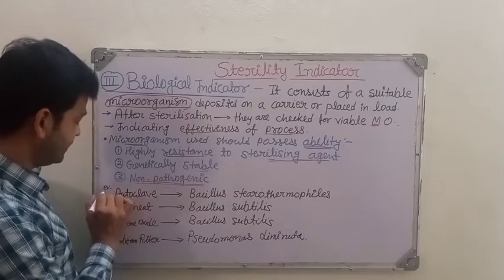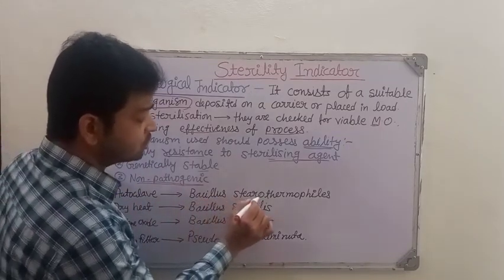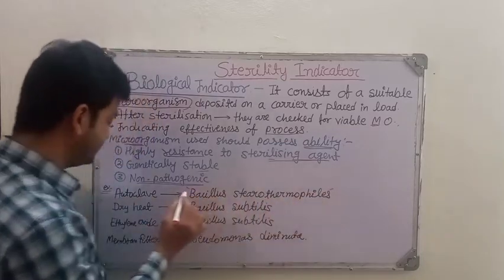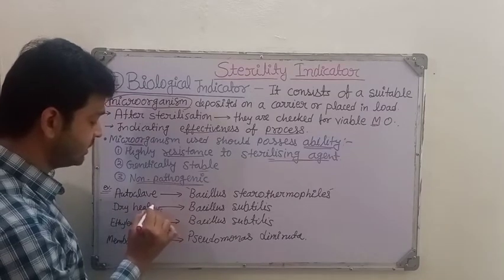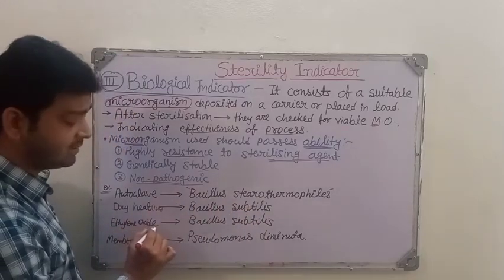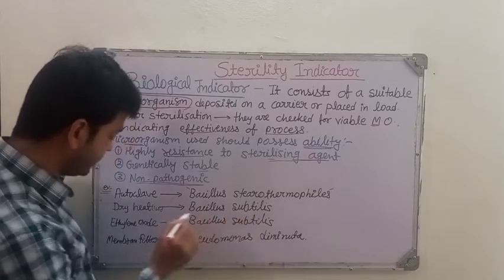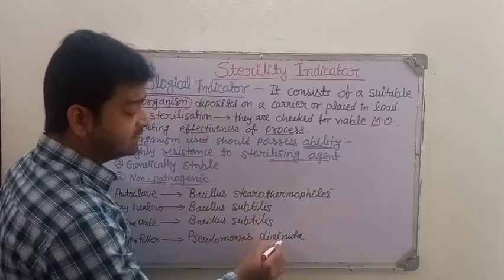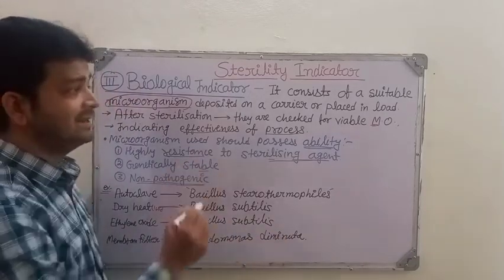For example, in autoclave sterilization, we use Bacillus stearothermophilus. In dry heat sterilization at 160 degrees centigrade, we use Bacillus subtilis. In ethylene oxide sterilization, we also use Bacillus subtilis. And for membrane filtration, Pseudomonas diminuta can be used as a biological indicator.